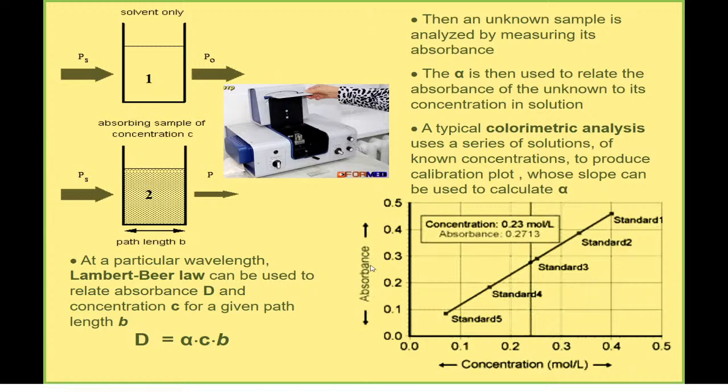This absorbance measurement is of two stages. First of all, you put on the way of the light the cuvette with the solvent only. After that, you look and see the absorbance of just the solvent, and you put, mechanically by handle, the reading equal to 0, and by that means you subtract the absorption by the solvent.